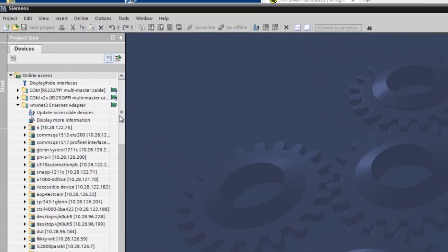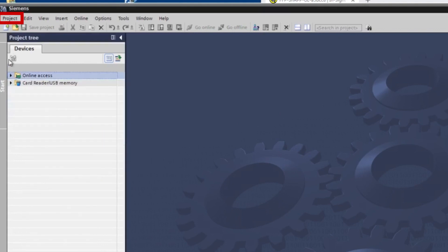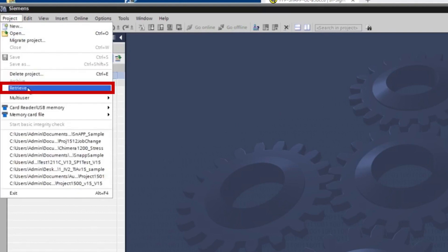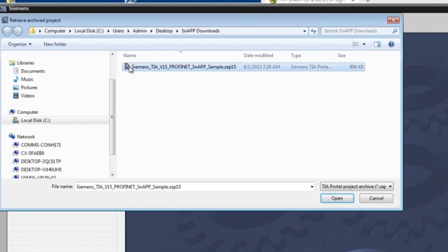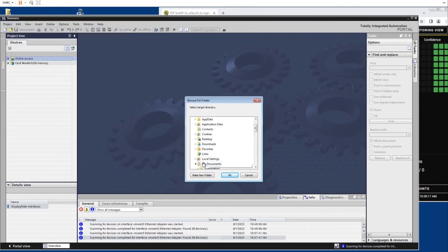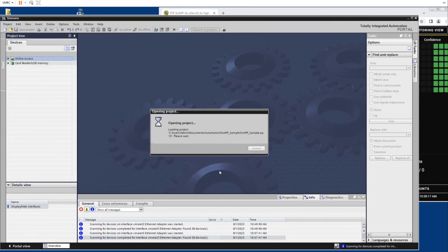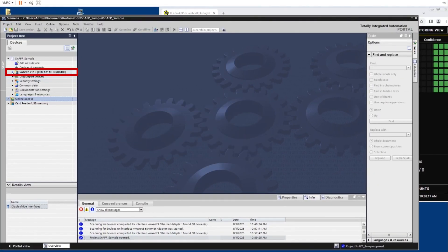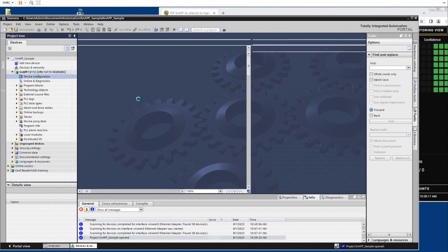We will use the PLC project that was downloaded from cognex.com and the GSD file. Click the project menu and then click retrieve. Locate and click on the downloaded project file to open and store it in a folder. Once the project file is stored, navigate to the InSight snap folder under Devices and click Device Configuration to see the PLC.